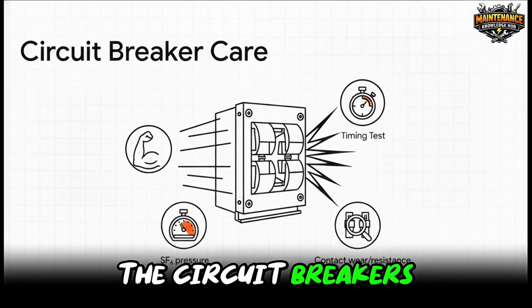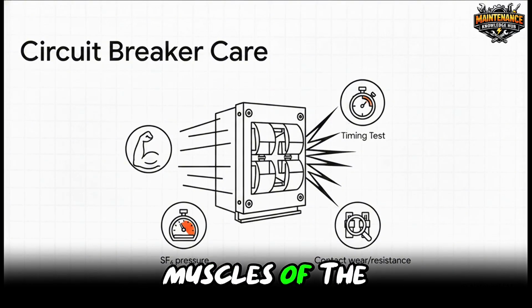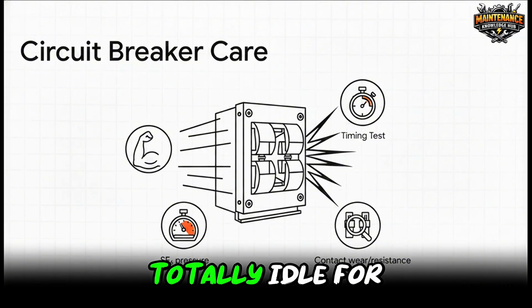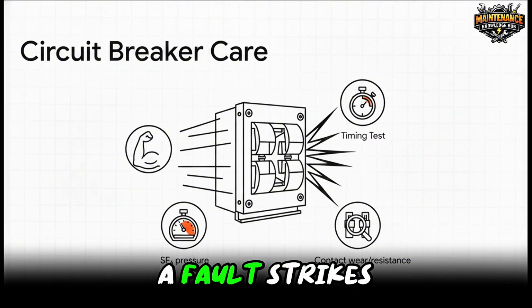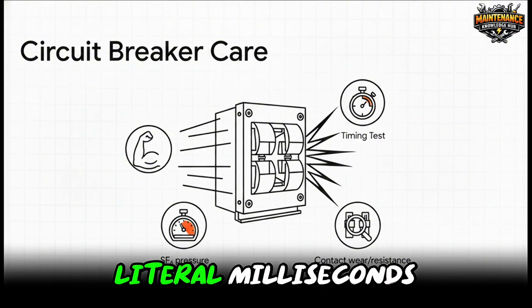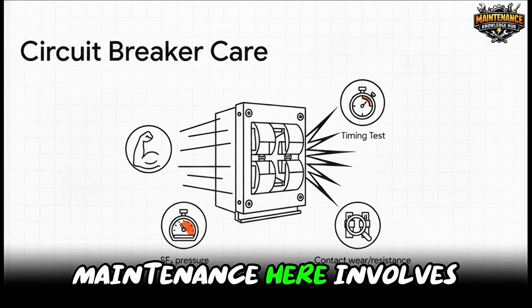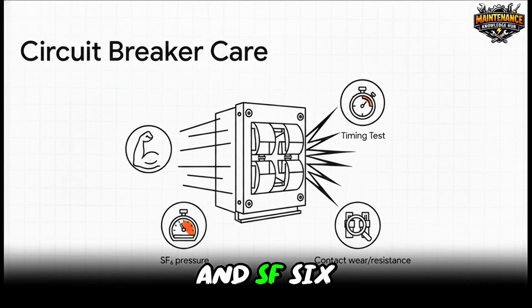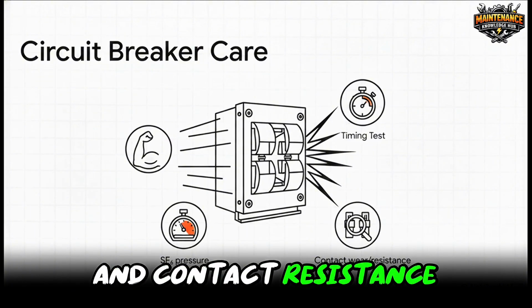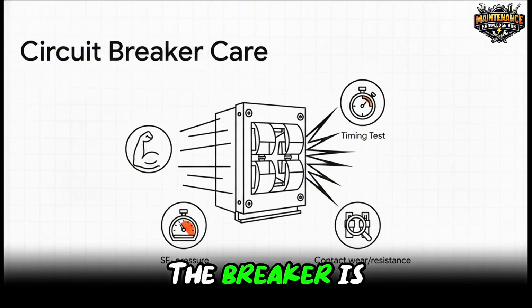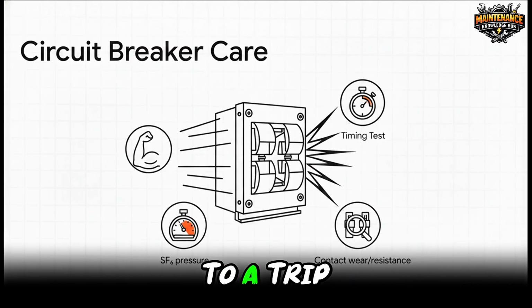Next, we've got the circuit breakers. Again, these are the muscles of the substation. They might sit totally idle for months on end, but the second a fault strikes, they have to snap open in literal milliseconds. Maintenance here involves inspecting contact wear and SF6 pressure, sure, but the real proof is in the timing and contact resistance tests. That's what ensures the breaker is going to react instantly and cleanly to a trip command.